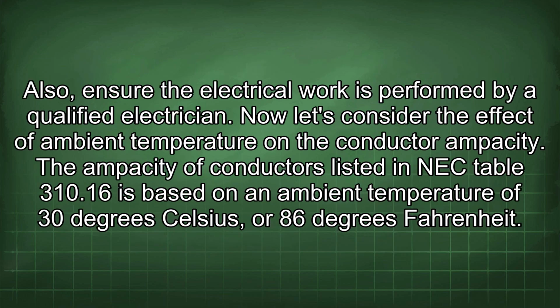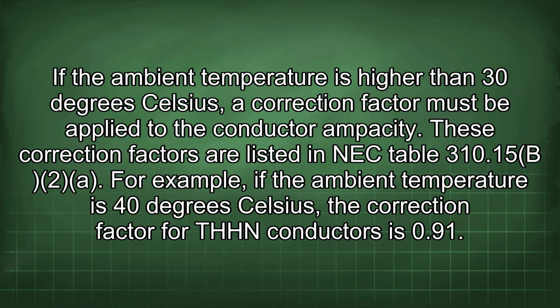Also, ensure the electrical work is performed by a qualified electrician. Now let's consider the effect of ambient temperature on the conductor ampacity. The ampacity of conductors listed in NEC Table 310.16 is based on an ambient temperature of 30 degrees Celsius or 86 degrees Fahrenheit.